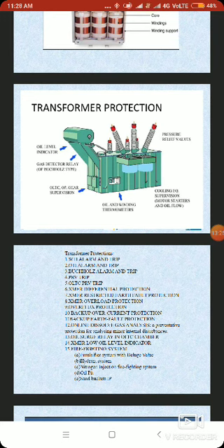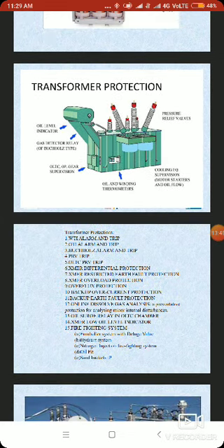Normally, whatever gas is accumulated inside the transformer, the float normally tips. Then PRV, pressure release device, which we discussed, there is a pressure release valve. So if the transformer gets pressurized, then this operates. Then OLTC PRV trip, we have got a separate one for that.